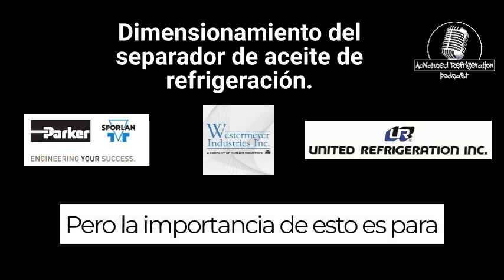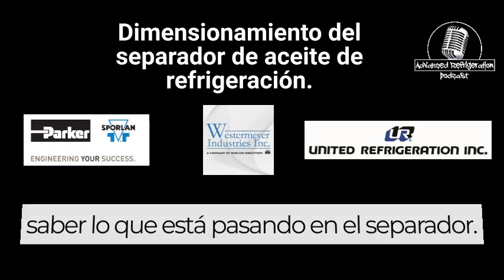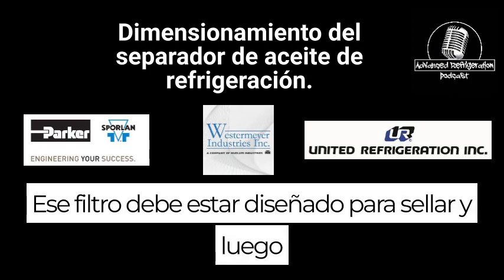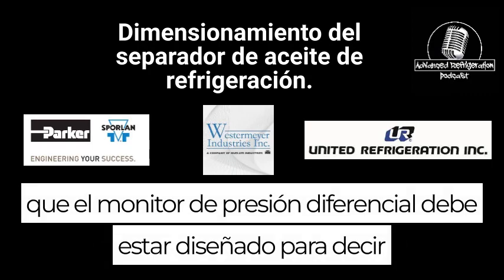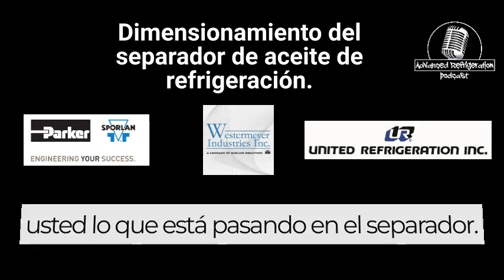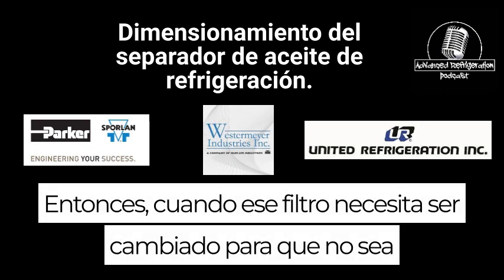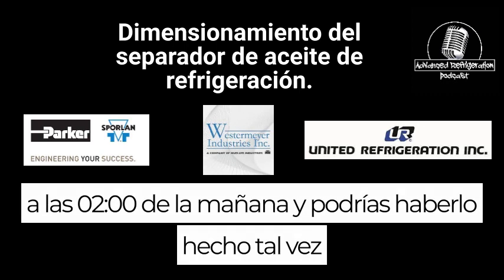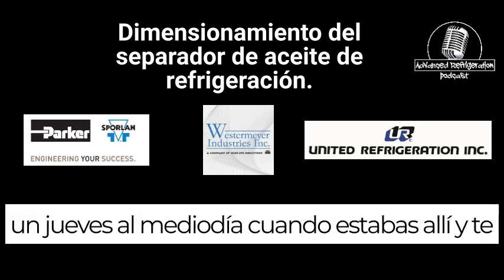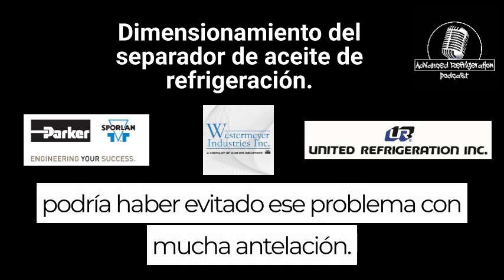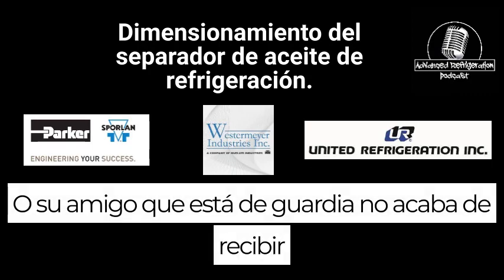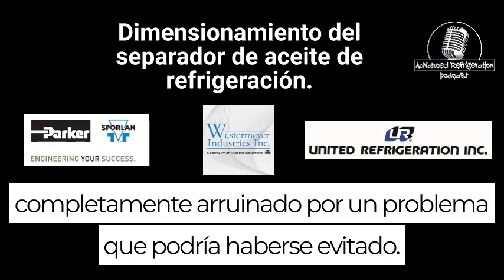But the importance of this is to know what's going on in the separator. That filter should be designed to seal, and then that differential pressure monitor should be designed to tell you what's going on in the separator. So when that filter needs to be changed, it's not at 2 o'clock in the morning. You could have done that maybe on a Thursday at noon when you were in there, and you could have headed off that problem well in advance, or your buddy that is on call didn't just get completely blasted by a problem that could have been prevented.